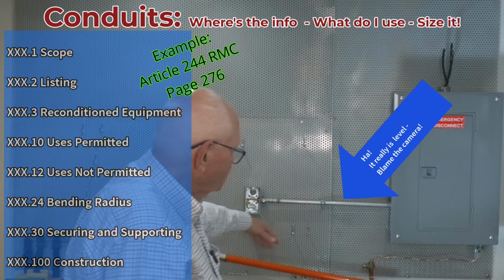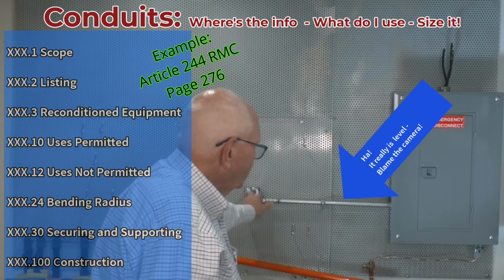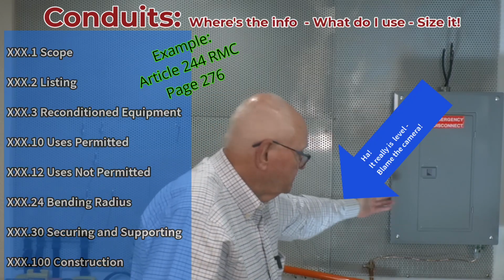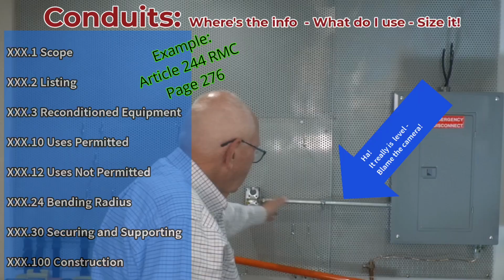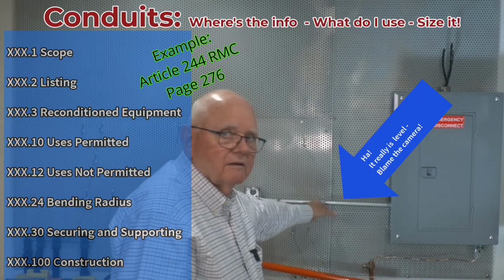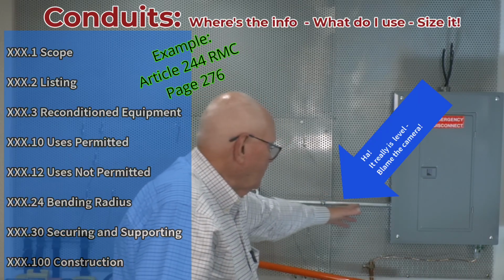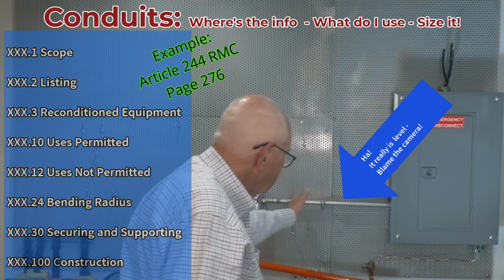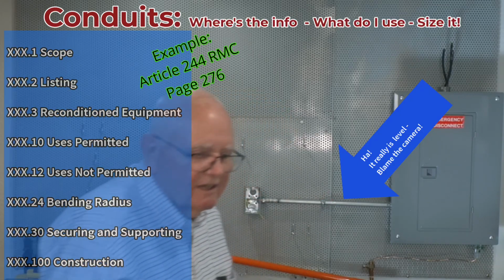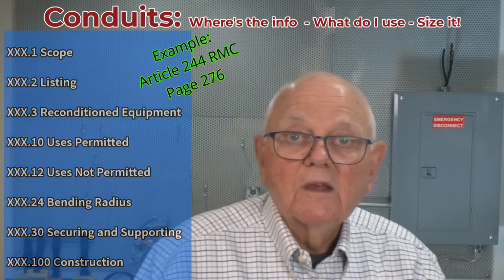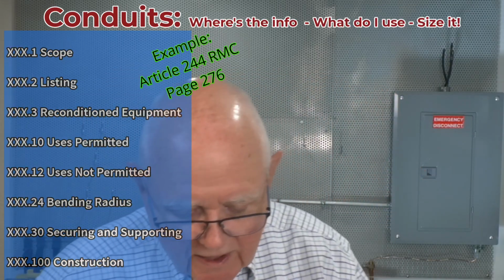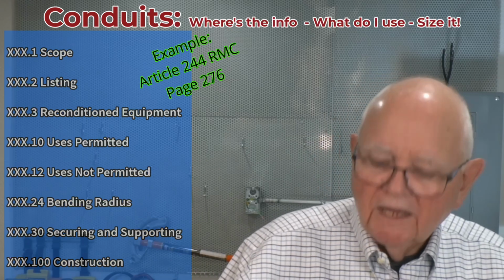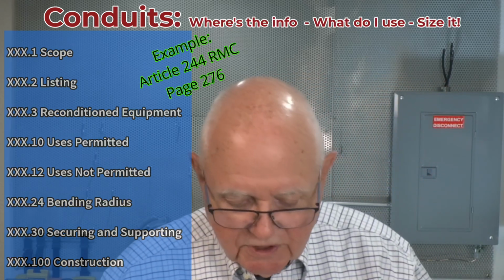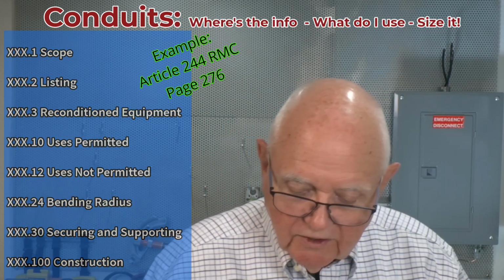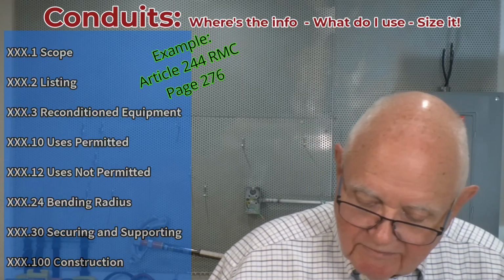And here, this is a fairly short run of EMT between the box and the panel board. And so by putting just one support in the middle, I'm able to meet that requirement. I'm right at a little less than 12 inches anyway. So I'll meet that requirement for supporting within 12 inches of the box on that particular conduit. But once again, each conduit, you're going to follow those specific conduit requirements for supports.